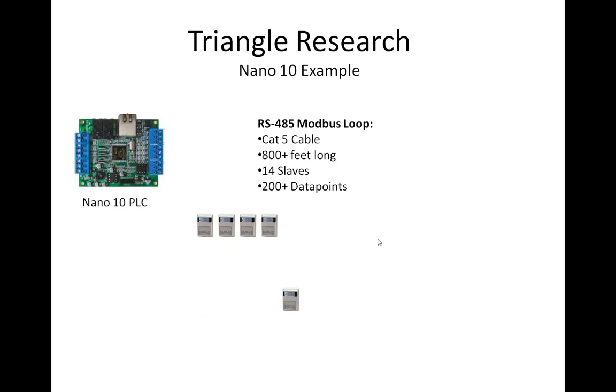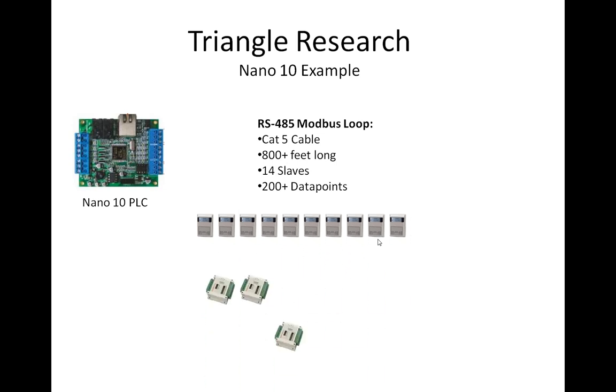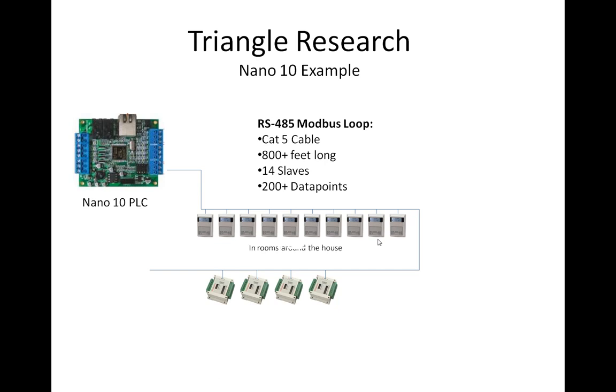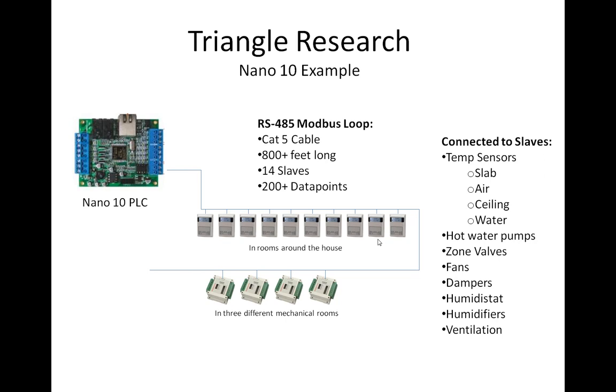The way we're using the Nano 10 is that all of our sensors and output devices are all on a slave network. It's on an RS-485 Modbus loop, which is about 800 feet long. We have 10 thermostats throughout the house, in the bedrooms and living rooms in different areas. We also have four input-output devices located in several different mechanical rooms. The thermostats have things like temperature sensors — sensing the slab temperature, air temperatures, and ceiling temperatures.